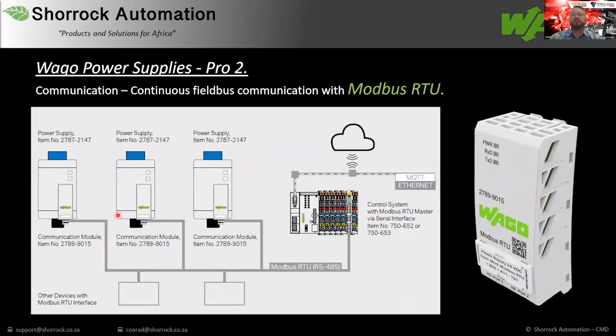In addition, we also have the Modbus RTU unit available, and here we can see it connected to a serial card to the WAGO PLC, or we can use that serial card if the serial different devices. What's nice about the WAGO Modbus RTU module is that it has two ports at the bottom. Now, Modbus RTU is quite easy to daisy chain, and we use a standard RJ45 plug at the bottom. And standard Ethernet cable in between the different devices, and then pull this data back to your device.